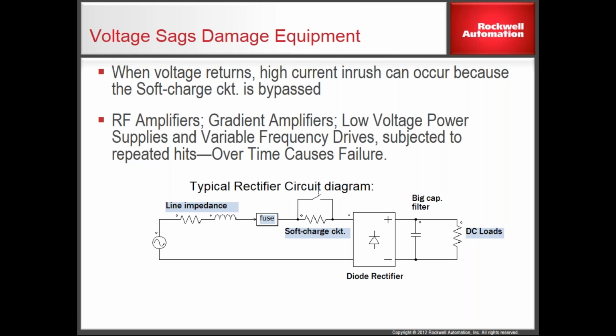Along comes our squirrel. We end up with a voltage sag, and all the electrons that were on our capacitor just took off and went to ground. Immediately the power supply needs to be charged up again, it's hungry for energy. So at the very end of the voltage sag, a current inrush takes place to charge those caps back up to where they should be. But since nobody ever shut it off, the bypass still exists around the soft charge circuit.